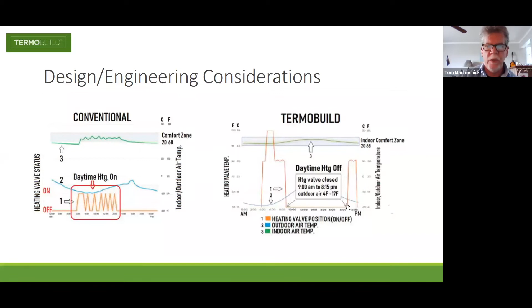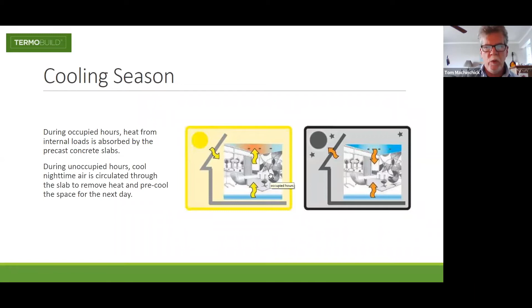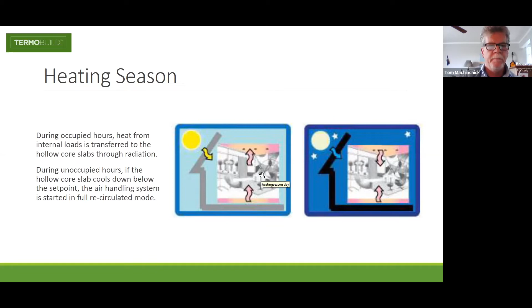So during cooling season, the heat from internal loads is absorbed by the precast concrete slabs. And during the night when it's unoccupied, cool nighttime air, fresh air from outside, is brought through the slab to remove the heat from the day that was absorbed from the people and the event. So it pre-cools the slabs for the next day. During heating season, during occupied hours, as we saw in the graph two slides ago, heat from the occupants is absorbed into the building and transferred to the hollow core slabs through just normal radiation. During the nighttime hours, recirculation can take place to take that heat that was gained during the day in the building. So without turning on the heating system, we use the heat that was generated in the building naturally to heat the building at night and maintain comfortable temperatures.